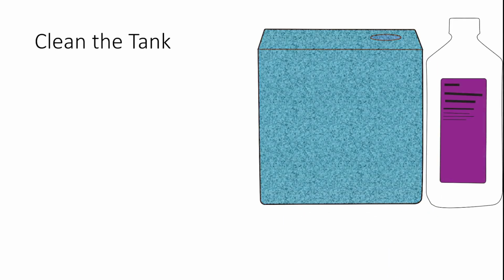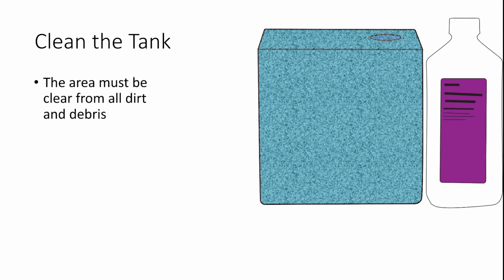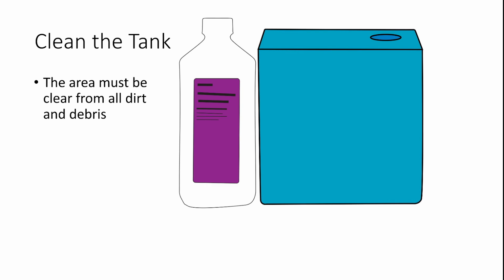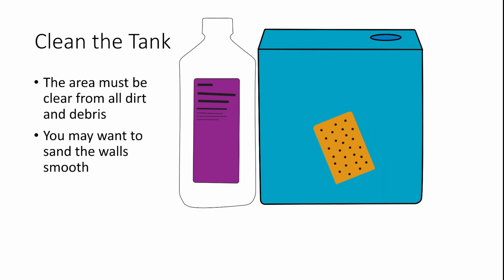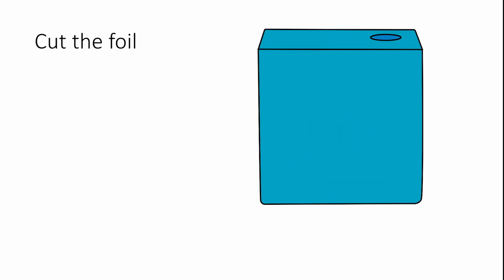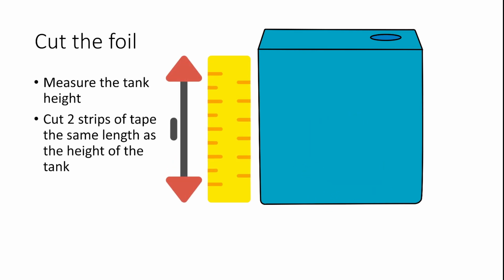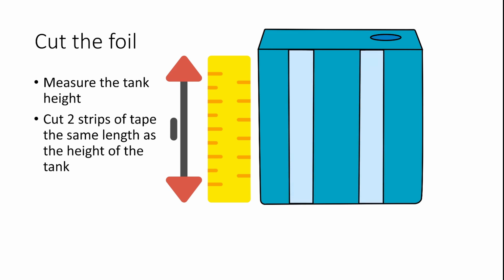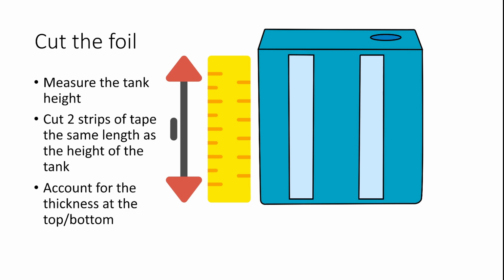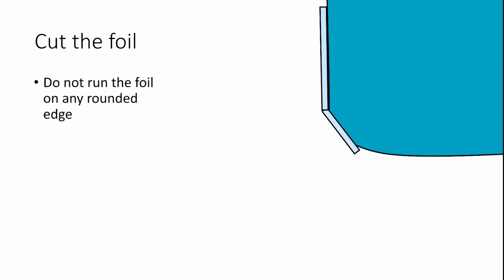Clean the tank. Clean the side of the tank with isopropyl alcohol where you will install the sensor. It must be free of all dirt and debris. If you have walls that are not very smooth, you may want to sand them down a bit to make them smoother. Measure the height of the tank. Cut 2 strips the same length as the height of the tank. Make sure to account for the thickness at the top and bottom of the tank. Do not run the foil on any rounded edge on the top or bottom due to the possibility of creating a peeling point on the tape.